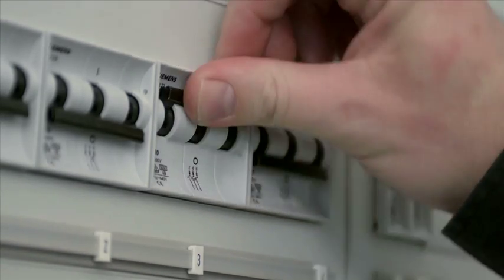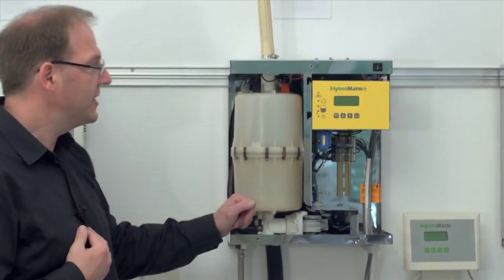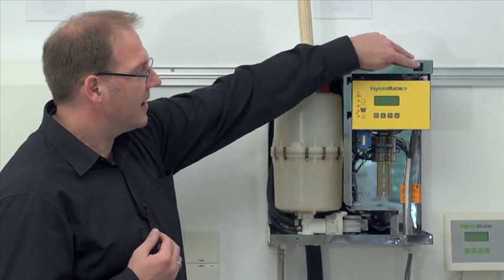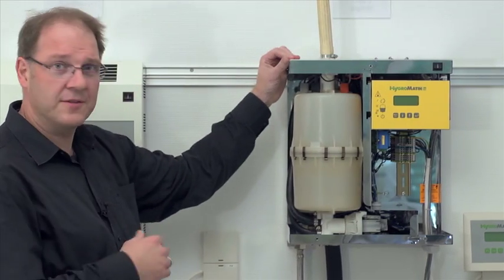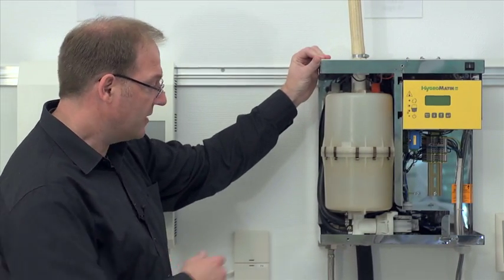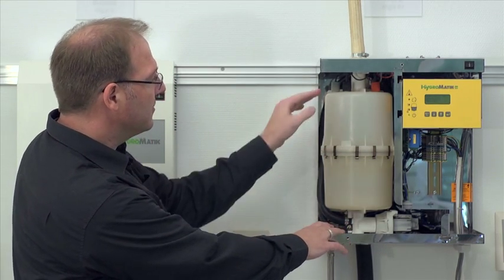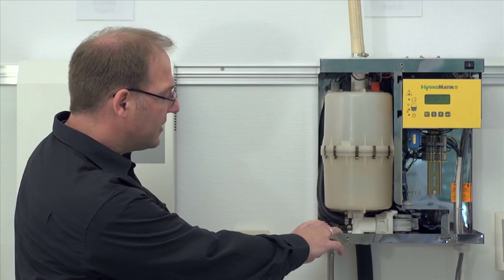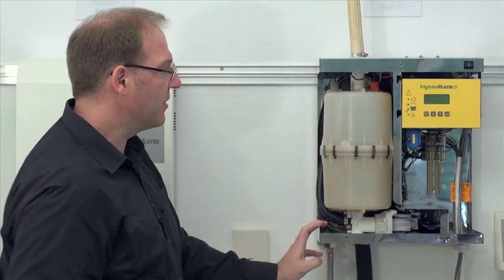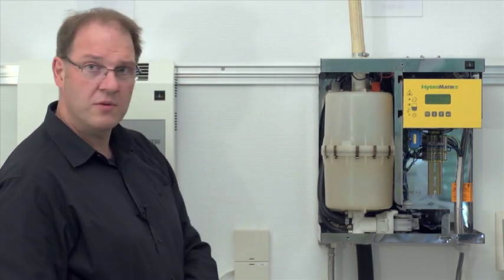After I have now reconnected the power supply, I restart the unit and let it run for five to ten minutes. I check during this time if everything is sealed properly, if the hoses and the seals are not emitting any water so far, and leave the unit running. All that is in order.